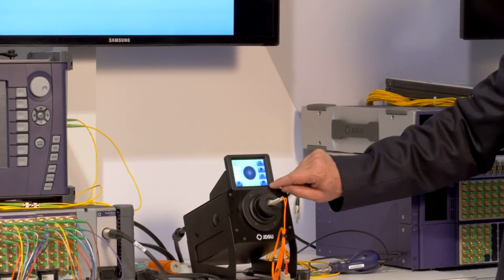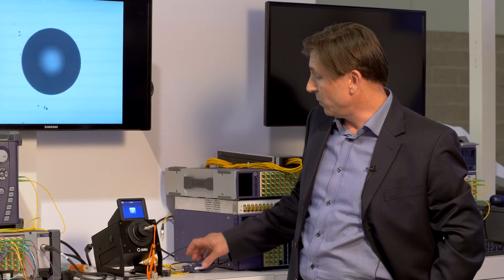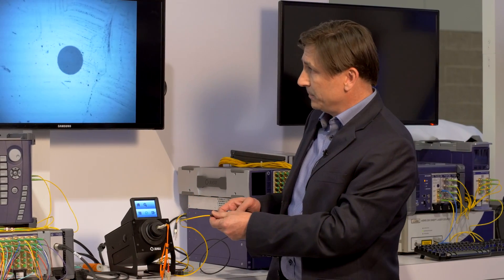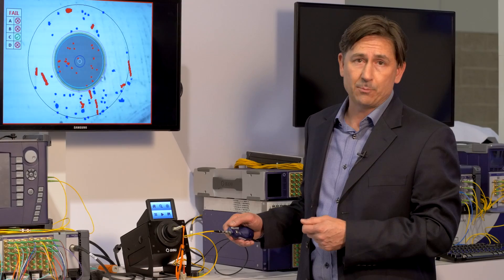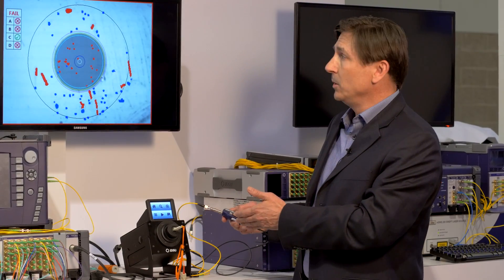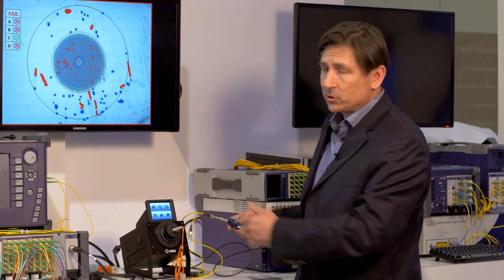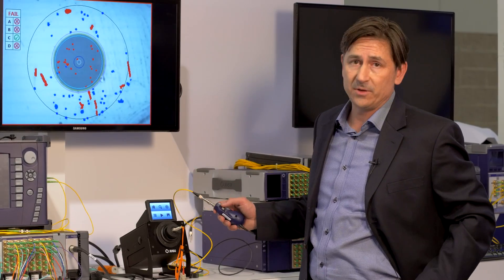The FVAI can also act as a host for other inspection devices, such as the P5000i probe. This enables the FVAI to act as a combined inspection workstation somewhere on your production line where a PC is not present, but you still want to do either probe inspection or benchtop patch cord inspection and provide pass-fail results.